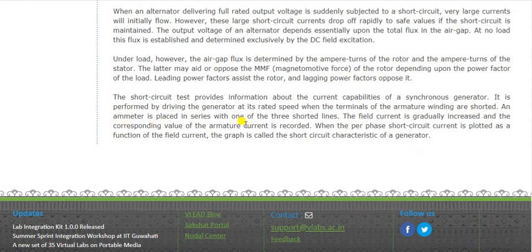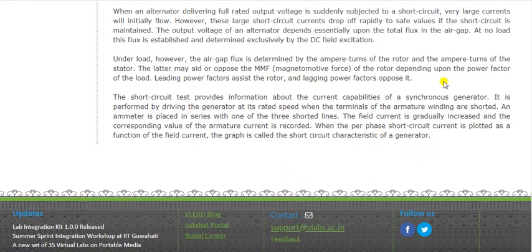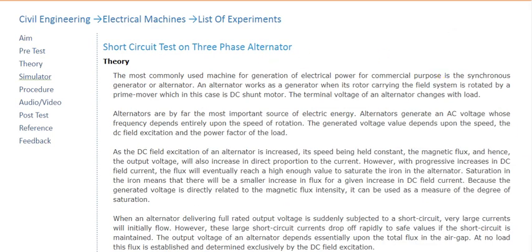The field current is gradually increased and the corresponding value of armature current is recorded. A graph is then drawn between field current on the x-axis and armature current on the y-axis. When the per-phase short circuit current is plotted as a function of the field current, the graph is called the short circuit characteristics of the generator.